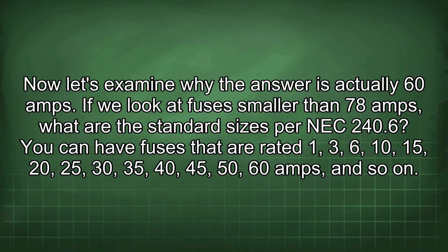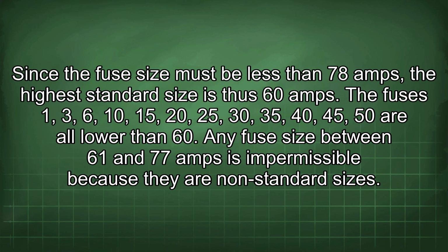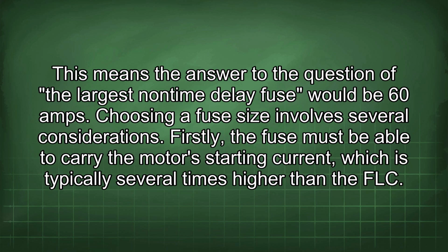If we look at fuses smaller than 78 amps, what are the standard sizes per NEC 240.6? You can have fuses that are rated 1, 3, 6, 10, 15, 20, 25, 30, 35, 40, 45, 50, 60 amps, and so on. Since the fuse size must be less than 78 amps, the highest standard size is thus 60 amps. The fuses 1, 3, 6, 10, 15, 20, 25, 30, 35, 40, 45, 50 are all lower than 60. Any fuse size between 61 and 77 amps is impermissible because they are non-standard sizes. This means the answer to the question of the largest non-time delay fuse would be 60 amps.